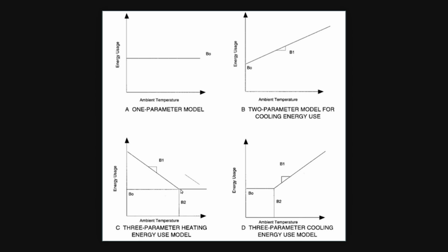If you wanted to characterize both hot water and heating of a building, you would use a 3-parameter model. In this case, the first parameter is the average consumption per day. The second parameter is the reference point. I mentioned 18 degrees Celsius is typically used by most standards. And then you have an increase per degree decrease of the average temperature outside.